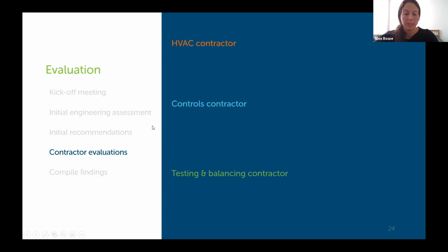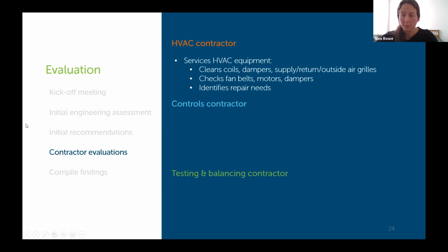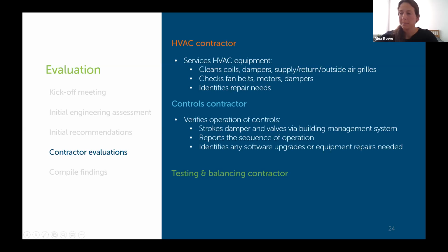So the customer then hired the contractors to dig into their mechanical system, and the HVAC contractor serviced the HVAC equipment, which included cleaning coils, dampers, supply and return and outside air grills, checking if fan belts are in decent condition or if they needed to be changed, if fan motors are operational or dysfunctional, and if dampers are in decent condition as well. They also identified any repair needs that existed at the time of the servicing.